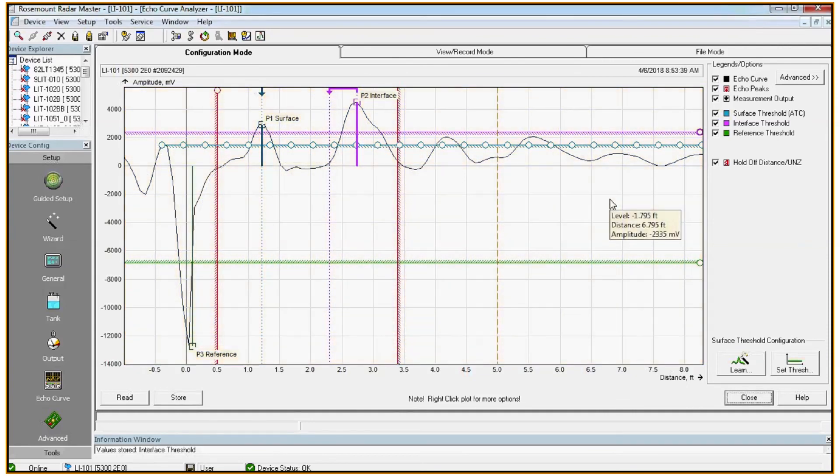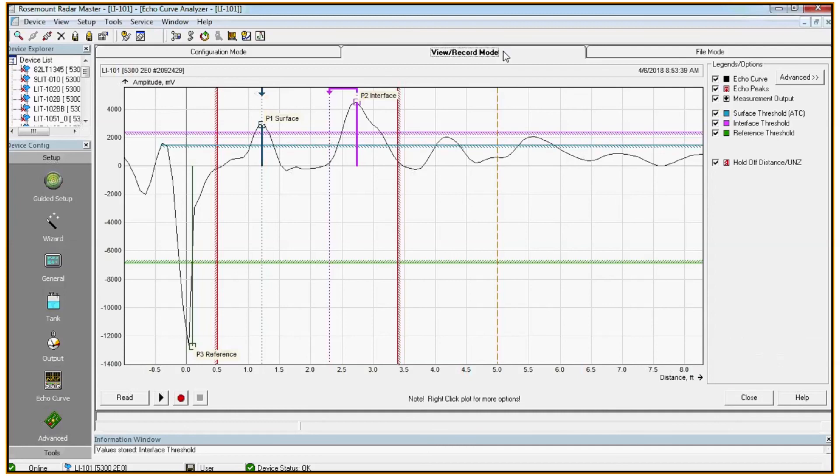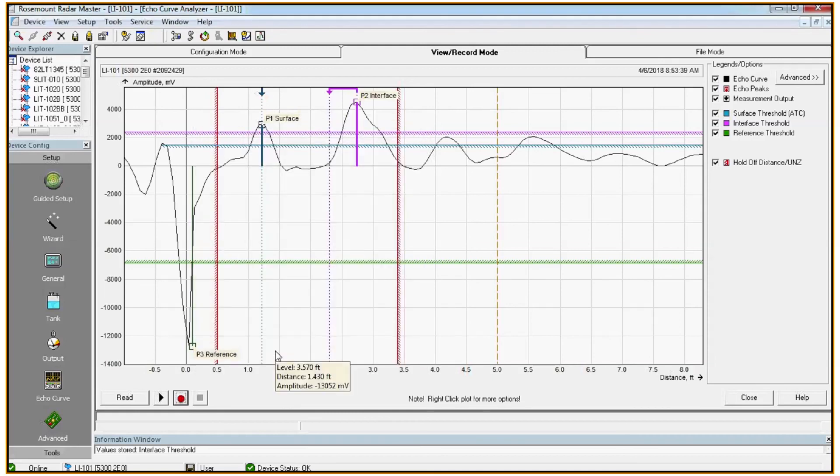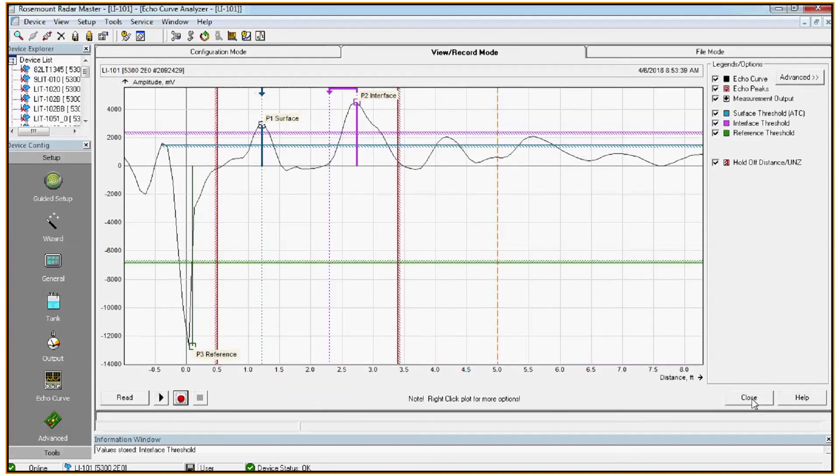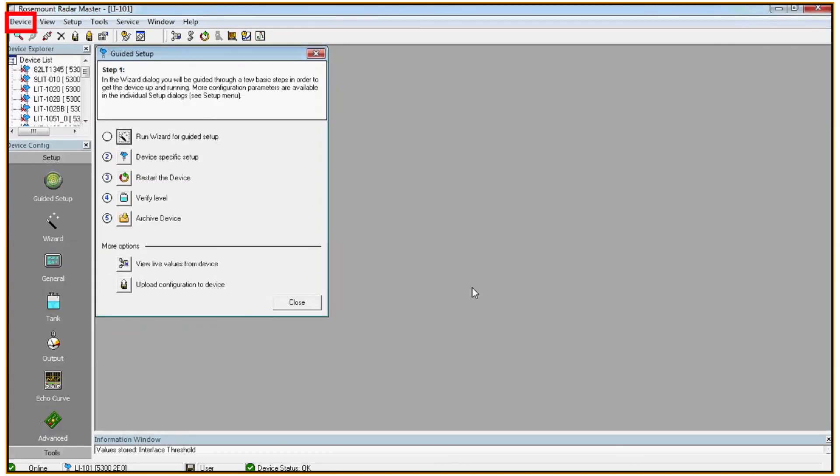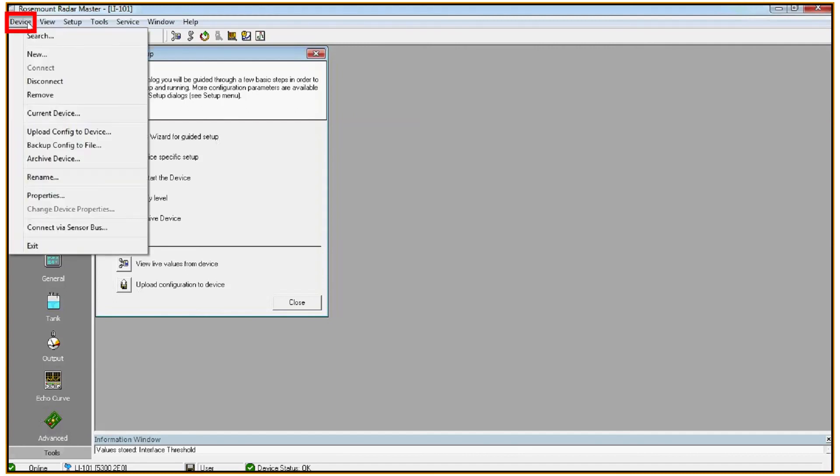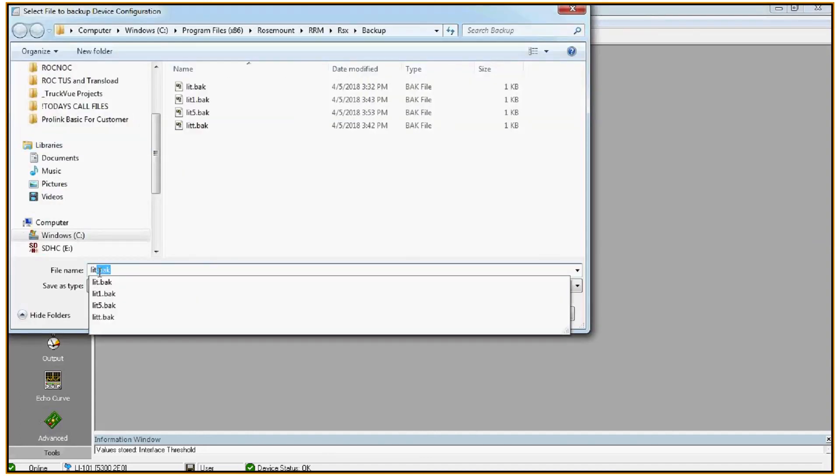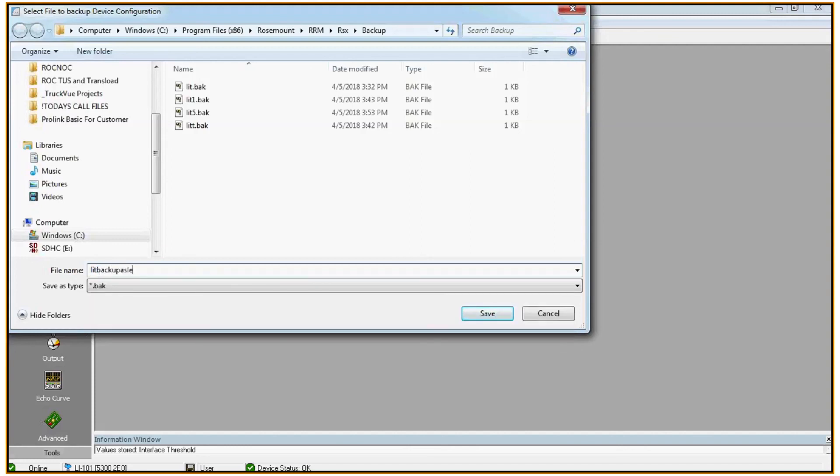Now that we've made a manual change to the echo curve settings, it's always a good idea to save another snapshot of the echo curve. So back to the view record mode tab. Click the red circle in the bottom left corner. Select save current snapshot to file and click OK. And the last thing we'll want to do is save a backup and as-left backup. So in the top left corner, click device, select backup config to file. Give the file name something you'll recall later and save it.